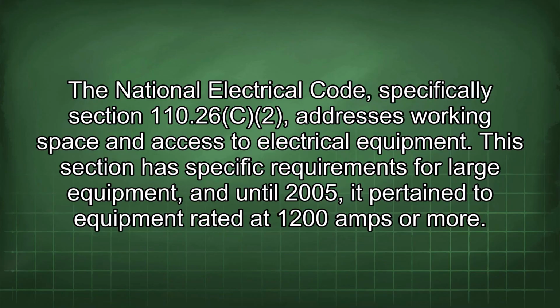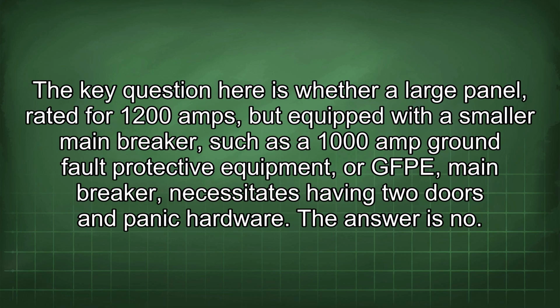The National Electrical Code, specifically Section 110.26C2, addresses working space and access to electrical equipment. This section has specific requirements for large equipment, and until 2005, it pertained to equipment rated at 1200 amps or more. The key question here is whether a large panel, rated for 1200 amps but equipped with a smaller main breaker such as a 1000 amp ground fault protective equipment or GFPE main breaker, necessitates having two doors and panic hardware. The answer is no.